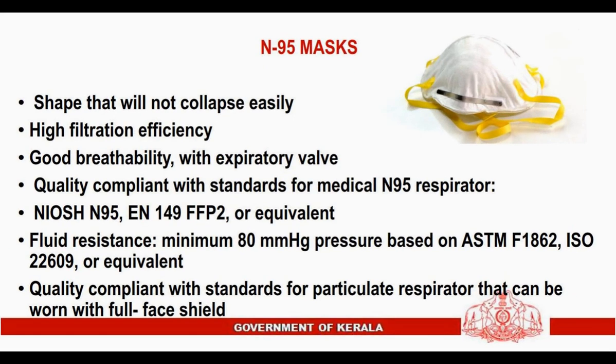N95 masks. Shape that will not collapse easily. High filtration efficiency. Good breathability, with expiratory valve. Quality compliant with standards for medical N95 respirator: NIOSH N95, EN 149 FFP2, or equivalent. Fluid resistance, minimum 80 mm of mercury pressure based on ASTM F1862, ISO 22609, or equivalent. Quality compliant with standards for particulate respirator that can be worn with full face shield.